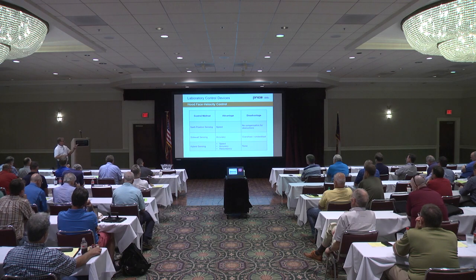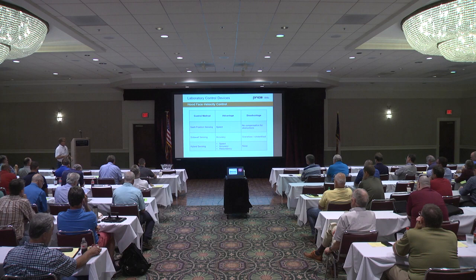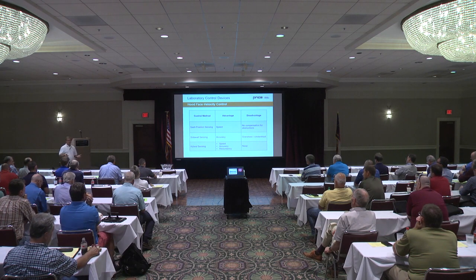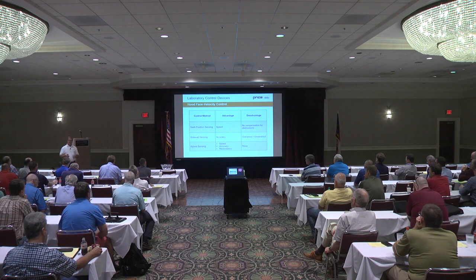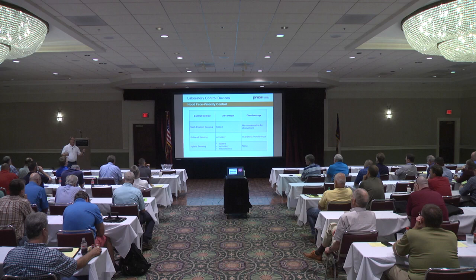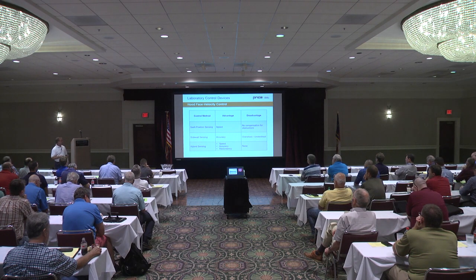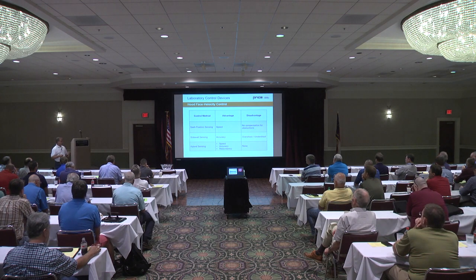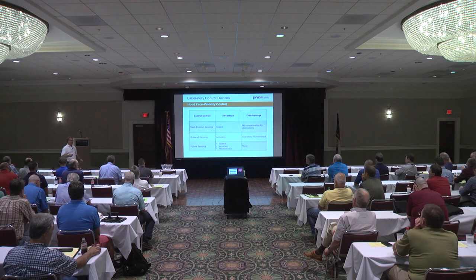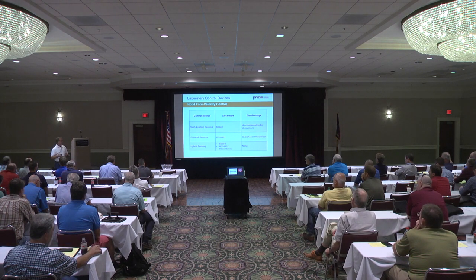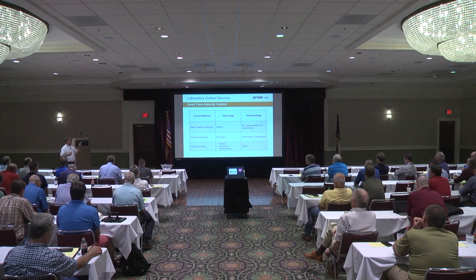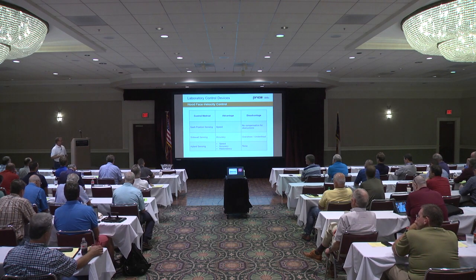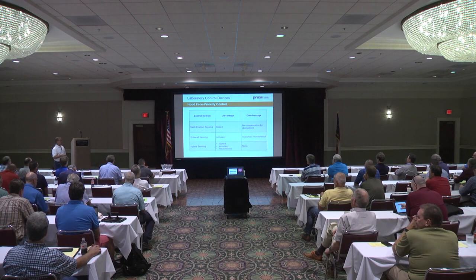Another method of doing a fume hood with combination sensors is hybrid sensing. You would use a sash sensor for the vertical portion, and you use a sidewall sensor for the overall reading, and you marry those two together to provide a signal to the valve to position it for airflow based on both pieces of information. So your sidewall sensing is for actual airflow measurement or velocity, and your sash sensor starts the process of moving the valve to the required flow position. So you start moving the sash, you immediately start moving the valve, and then you read the velocity at the same time to know when you've met your set point for velocity.